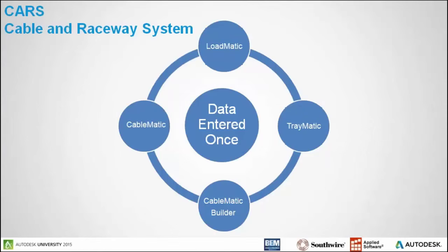I'd like to start off by talking about how we work today. Now, we all are in different industries, and we have a lot of different work processes and procedures that we may follow. But in its most basic sense, electrical doesn't change that much. We all do basically the same thing. We collect information from other disciplines, whether it's from a P&ID or an equipment list, and we compile a load list to do our electrical analysis so that we can size our buses, size our transformers, and all of our electrical systems.